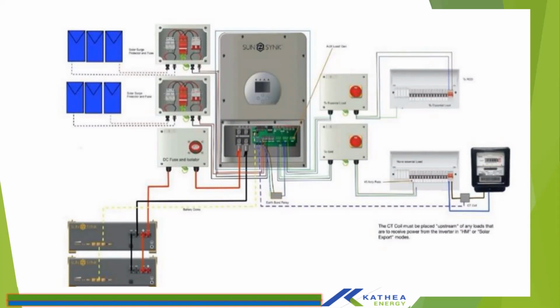And the fuse rating should be rated to the size of the inverter. If you are using an 8 kilowatt, the DC fuse rating is 190 amps. So something around a 200 amp fuse would do, or lesser than 190 would do, so as to protect both your inverter and your batteries as well.